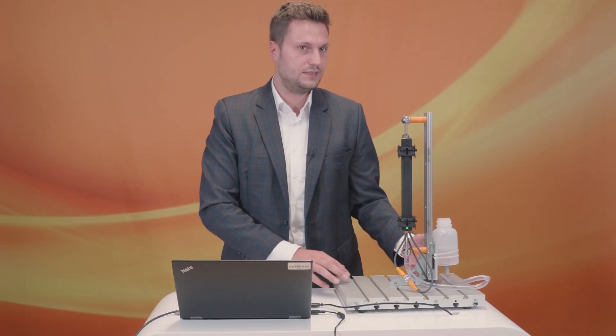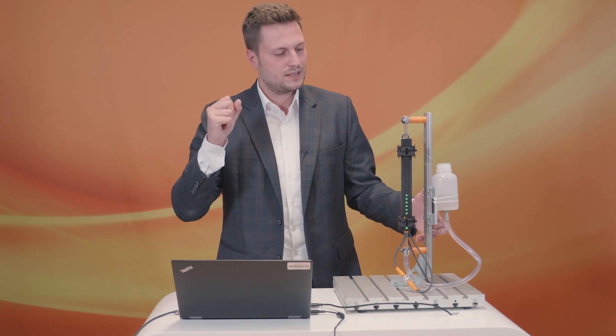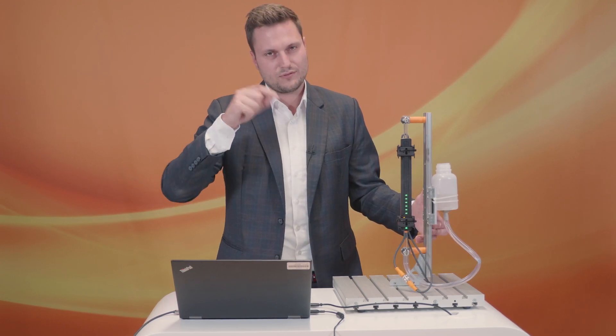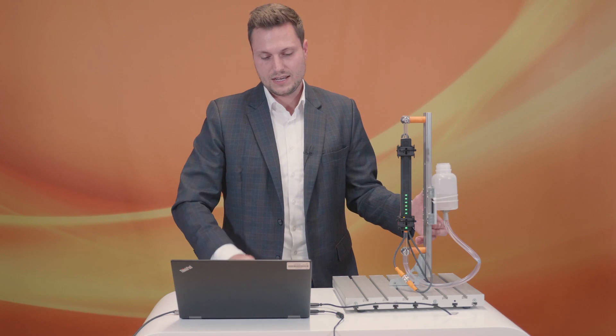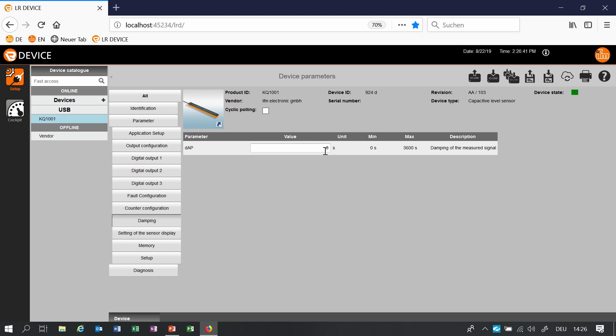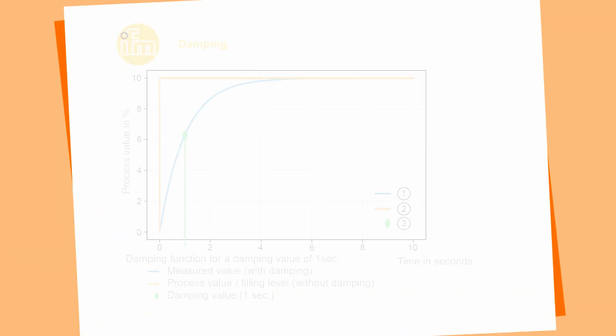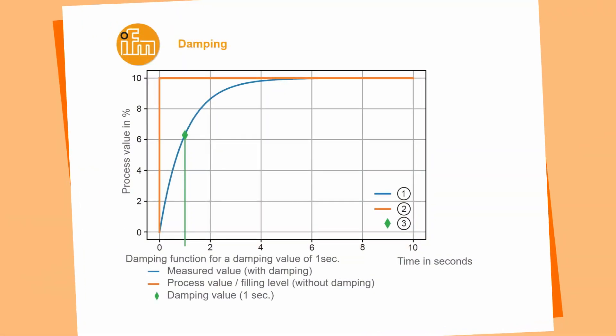When you have applications where the process value is rising very fast and you don't want to have a process value which is shooting from 0 to 10 or 50 or whatever we are able to set a damping inside of the sensor. So now I will set it at 3 and write it to the sensor. On this graph you can see the damping. Imagine you have a process value which is rising from 0 to in this case 10 and you want to have a very stable process value so you're implementing a damping for a second or three and you have a very nice curve of the process value.